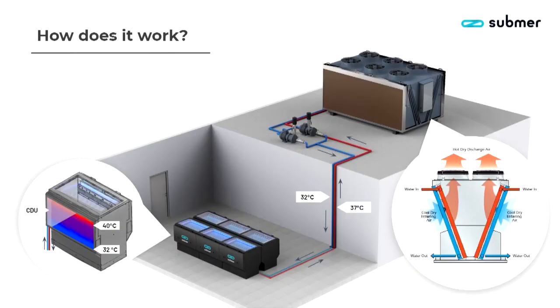And you can see from this slide that the temperature range at which we operate, and this is a very conservative temperature range, allows us to run the dry cooling infrastructure anywhere on the globe without having to chill the water.